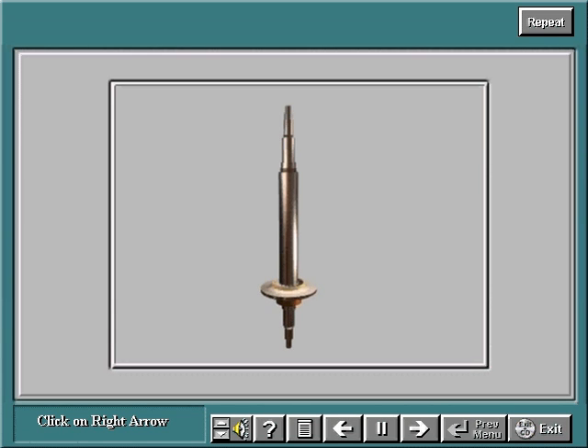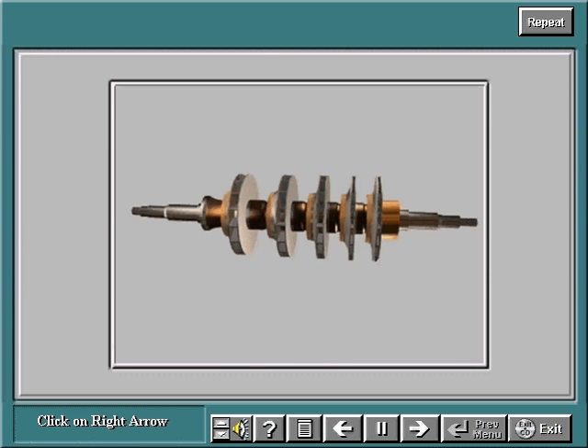After the partially assembled rotor has been balanced, a spacer is installed, the next impeller is added, and both are heat shrink fitted to the shaft. Then the rotor assembly is balanced again. The sequence of balancing the rotor, installing the spacer, and adding the impellers is repeated until the suction impeller, spacer, and locking ring are installed and balanced as defined by the customer requirements. Generally, the thrust collar is added last. It is hydraulically expanded and pressed into position on the end of the shaft.